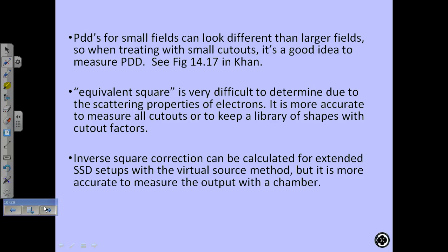Okay, so you want to consider that if your aperture gets smaller and your PDD changes, yet your doctor goes to your PDD tables, which are defined for an open cone, there's going to be misrepresentation of PDDs there. He might look at the table of PDDs that you have for open cones and say, well, this tumor is 3 cm deep, and it looks like the 12 MeV electrons cover 90%, so I'm going to choose 12 MeV. But in fact, that PDD could be different because it's got a different cutout, and so he might want to choose a higher energy.